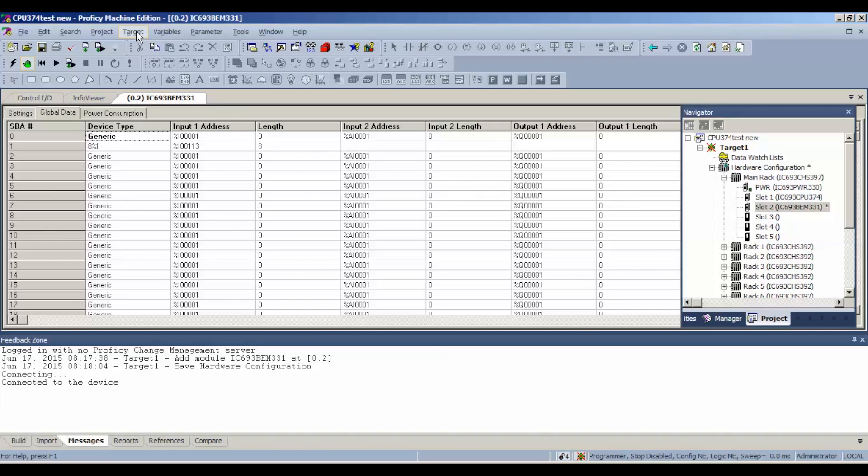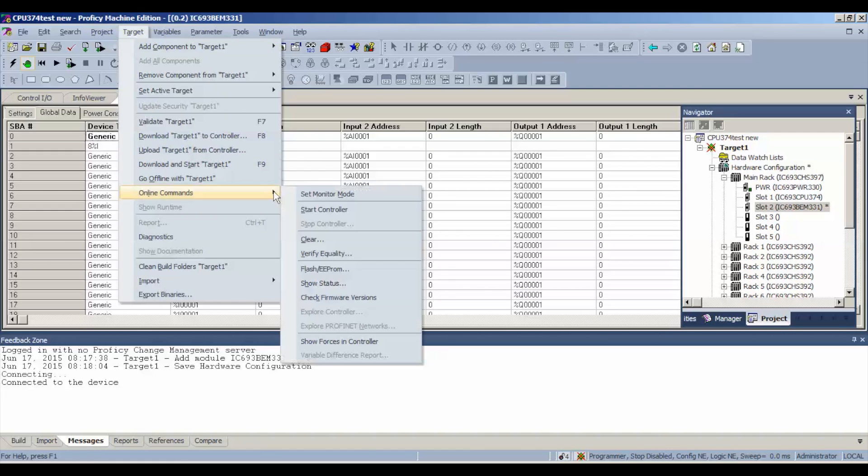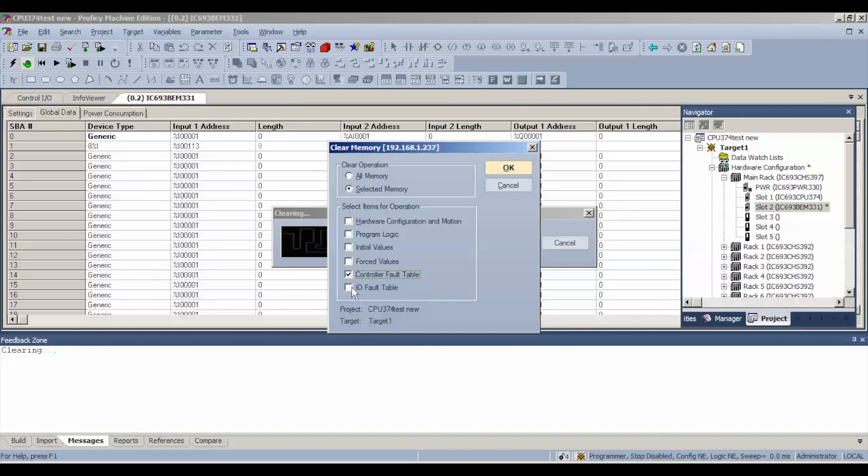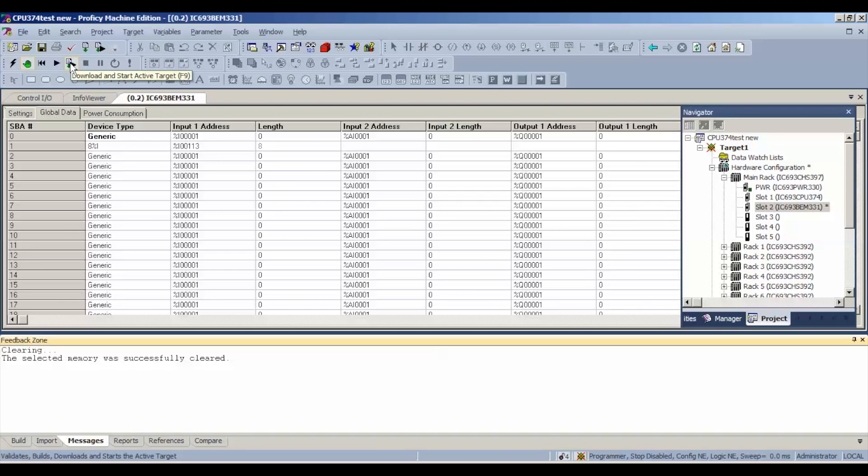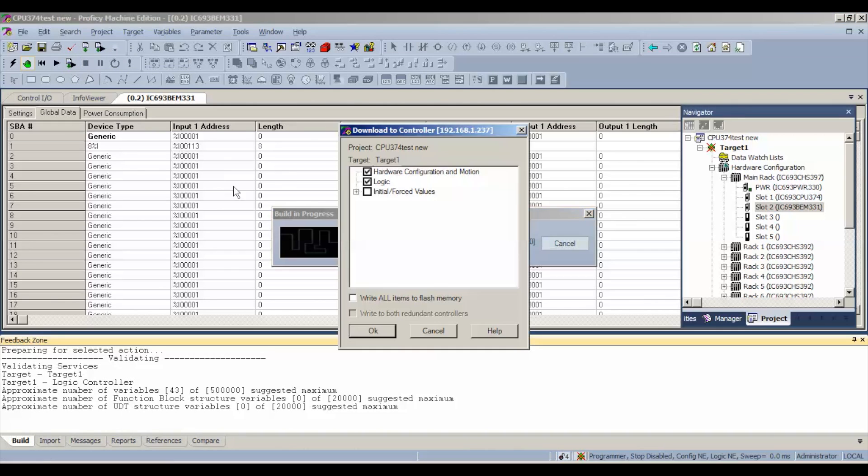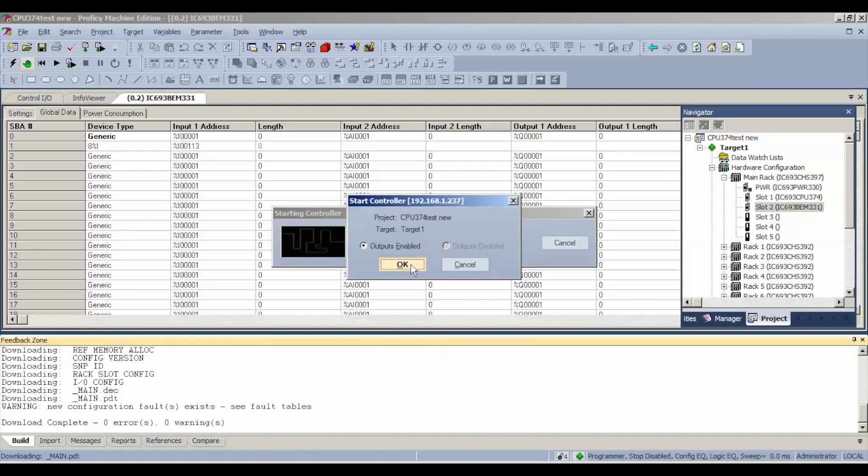Now, if you look down below, my status of the processor right now is programmer mode. It's stopped, meaning not in run mode. Inputs and outputs are disabled, and the configuration and logic are not equal. What we're going to do in that case is go to target, online commands, clear, controller and I/O fault tables. You want to do that to make sure we don't get hung up when we do this part of the download and start active target. For this test, it's just going to be hardware configuration and motion and logic. We don't need to write anything to permanent flash memory. Select okay and enable the outputs, yes.